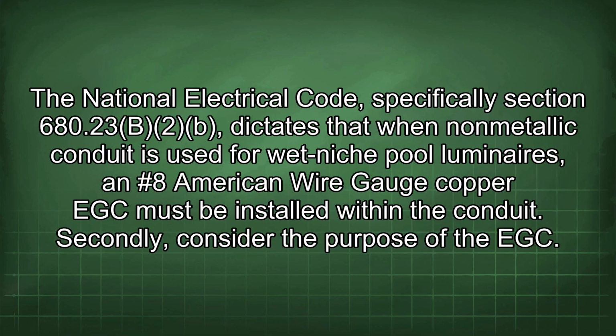The National Electrical Code, specifically Section 680.23(B)(2), dictates that when a nonmetallic conduit is used for wet niche pool luminaires, a #8 American wire gauge copper EGC must be installed within the conduit. Secondly, consider the purpose of the EGC.